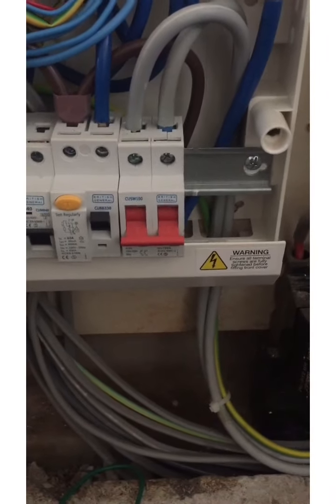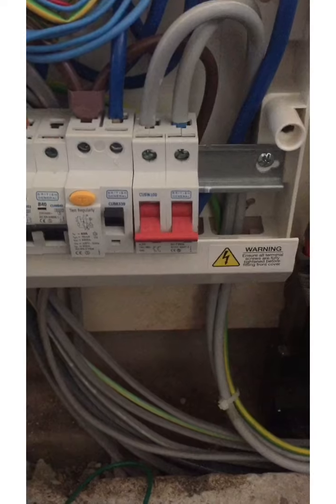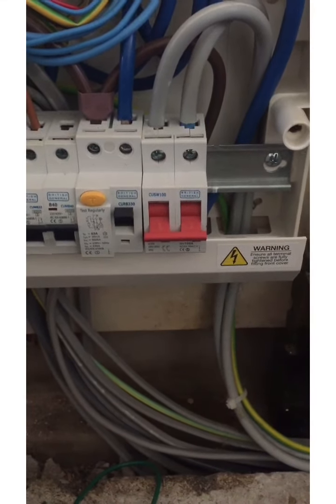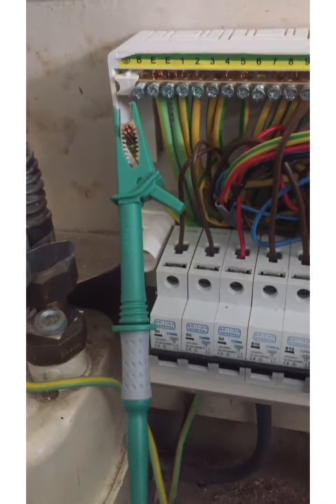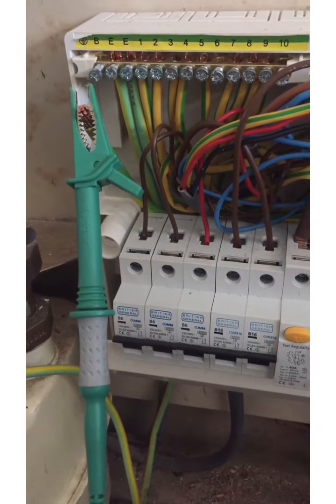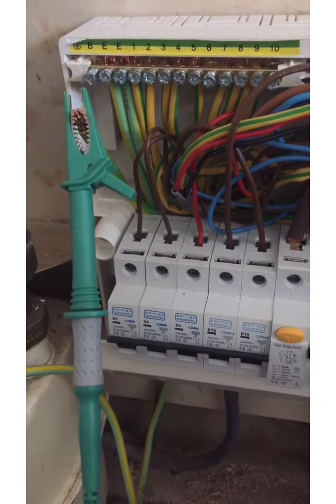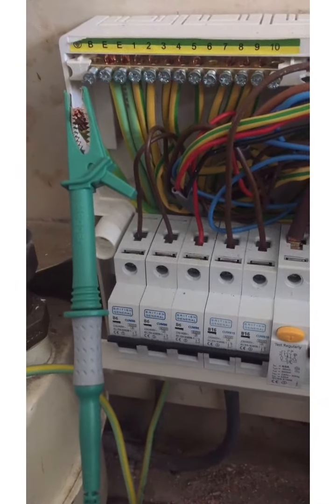So the board is isolated from the supply. The consumer is isolated from the supply, and one of the reasons is we've got the earthing conductor disconnected, so we don't want to risk people using the installation, obviously, with the earthing conductor disconnected. So that's the setup.